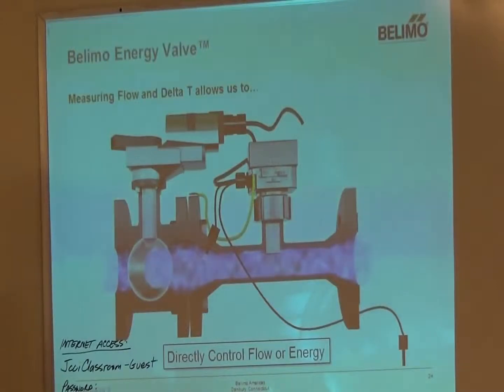Now on the energy side of things, the energy valve basically becomes one with the coil in that it knows the max BTU output of the coil. And this is the part that I haven't done as much, so if I say something wrong, Brian, jump right in. But basically what we're trying to do is control to the energy requirements of the room. So if it requires X amount of energy and we know the coil can do 2X, then the valve will get a 50% control signal, or it'll control to 50%, I should say, of that BTU requirement.